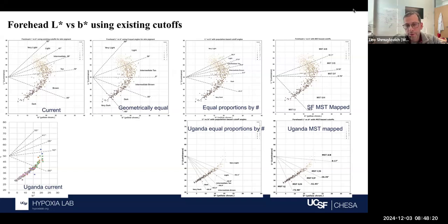But there are papers that demonstrate that if you put a blood pressure cuff on somebody and you measure ITA at the forearm before the cuff is on and after the cuff is on, even though their melanin didn't change, the ITA changes. So ITA is an imperfect surrogate for melanin. And if one were to come up with a better surrogate for melanin, that would be awesome.